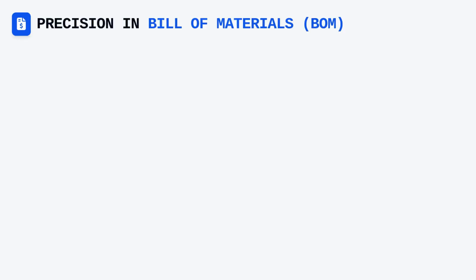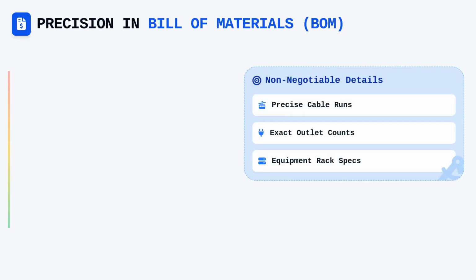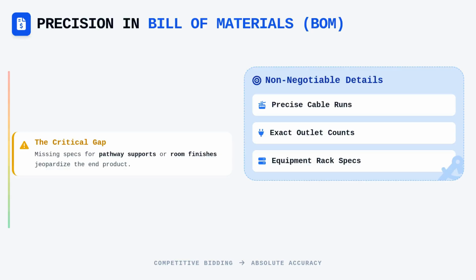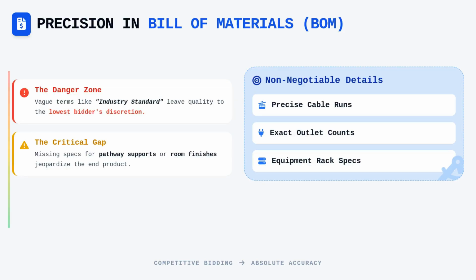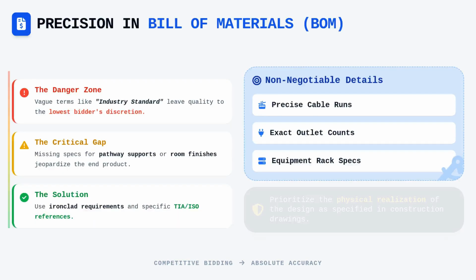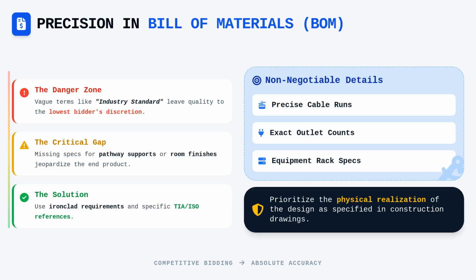Translating design drawings into a precise bill of materials is a task that leaves no room for error. Every cable run, outlet, and equipment rack must be accounted for to ensure that the bidding process remains competitive and accurate. When creating your contractual language, avoid using vague terms like industry standard without providing the specific TIA or ISO reference where that standard is formally defined. If you lack a clear requirement for how a pathway must be supported or how telecommunications rooms must be finished, you are leaving the quality of the end product to the discretion of the lowest bidder. Instead, write ironclad requirements that prioritize the physical realization of the design as specified in your construction drawings.